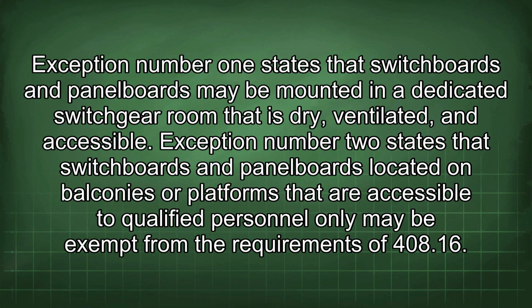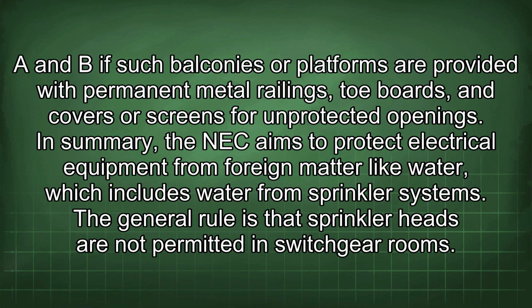Exception number 1 states that switchboards and panel boards may be mounted in a dedicated switchgear room that is dry, ventilated, and accessible. Exception number 2 states that switchboards and panel boards located on balconies or platforms that are accessible to qualified personnel only may be exempt from the requirements of 408.16 A and B if such balconies or platforms are provided with permanent metal railings, toe boards, and covers or screens for unprotected openings.